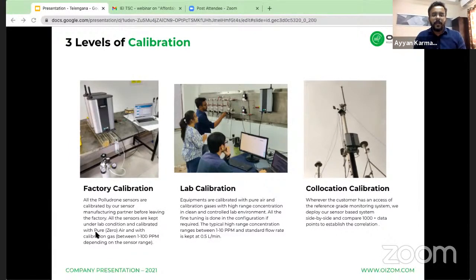Firstly, there is a factory calibration, where the right mixture of gases is passed through each sensor to validate the sensitivity. Then comes the lab calibration, where there is a multi-point span calibration. We use a dilution system with SI traceable gases. For example, 550 ppm of CO can be diluted to 50 ppb, 500 ppb and 5 ppm, and we ensure that we account for any cross sensitivity or other such interferences. And lastly is a collocation calibration.